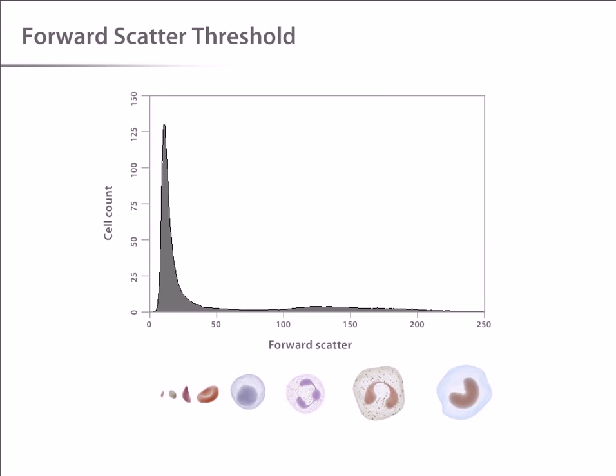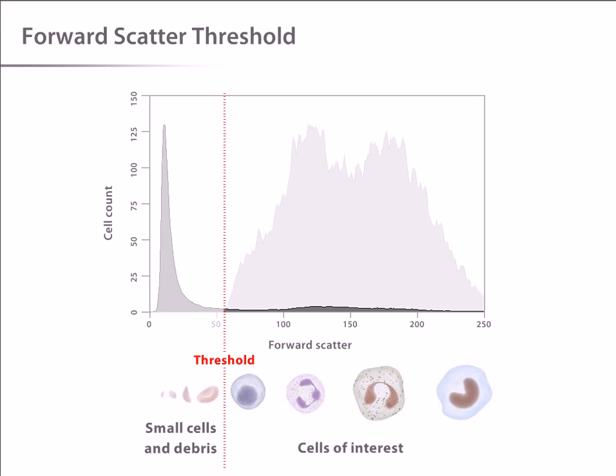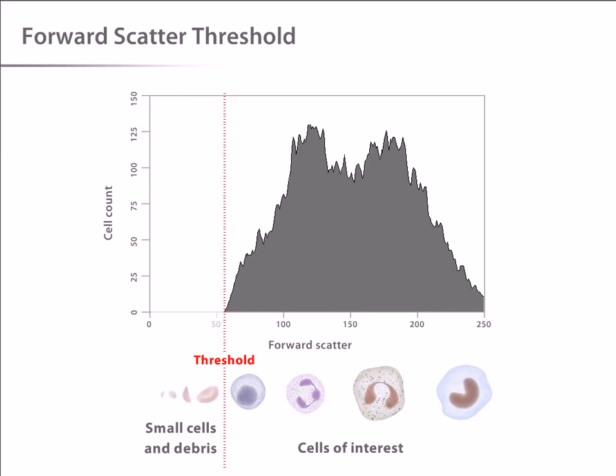One final important point regarding data collection is the use of a threshold. If every single particle passing through the laser caused the instrument to collect data, the data pool would be dominated by information coming from a very large number of minute particles like platelets and debris. To prevent this, a threshold is set such that a certain forward scatter pulse size must be exceeded for the instrument to collect the data. On the histogram, the blank area represents the small cells and debris that are excluded from analysis by the threshold. This means that the majority of events that the cytometer collects are the cells of interest. It is important to realize that the small particles are still passing through the instrument, they are just being ignored.